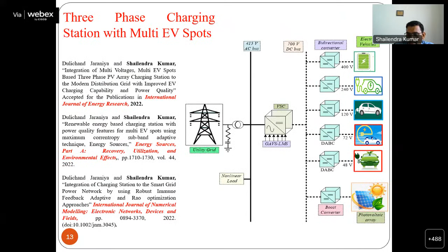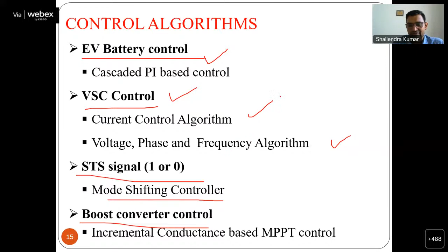Also the voltage IGBTs, and here we have used some control. So what would be the control algorithm involved in these particular converters? EV battery control is required, VSC control is also required. VSC control is nothing but current control as well as voltage control. On the other side, we require mode shifting control also, current control to voltage control and voltage control to current control. The boost converter control is also required, and here a simple MPPT will be used to extract the maximum power as we are using a two-stage system.